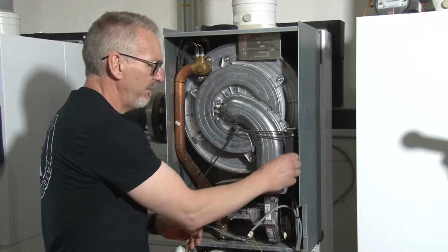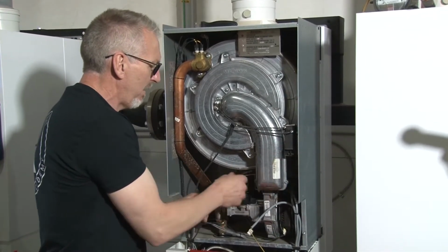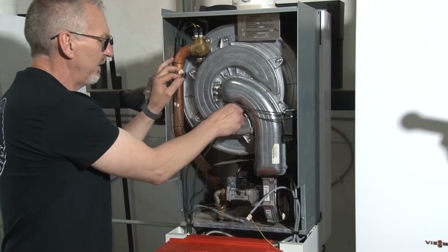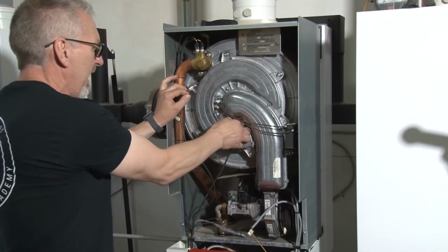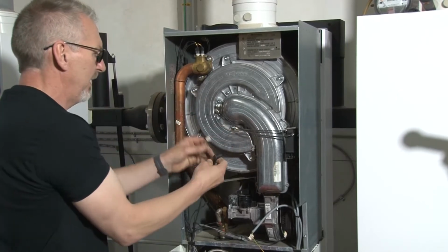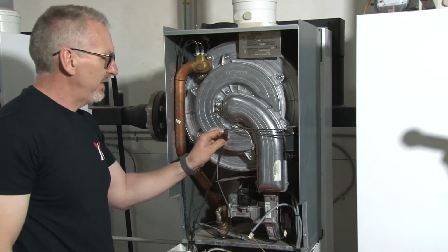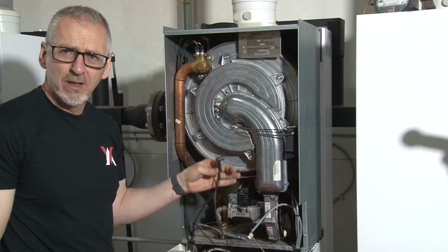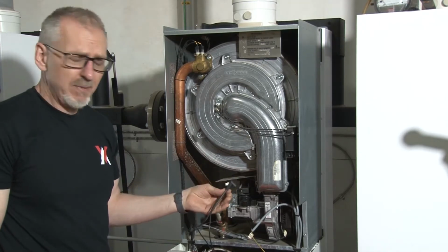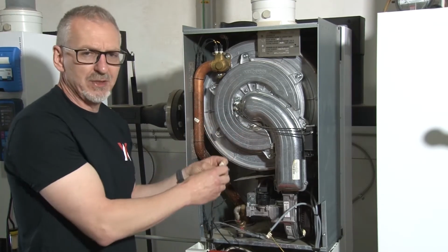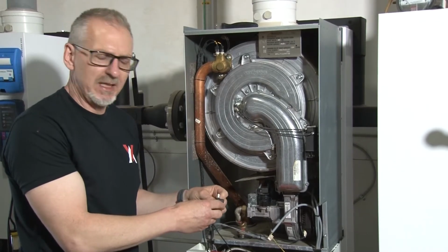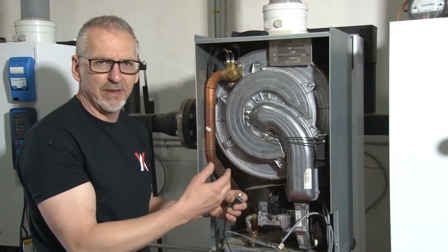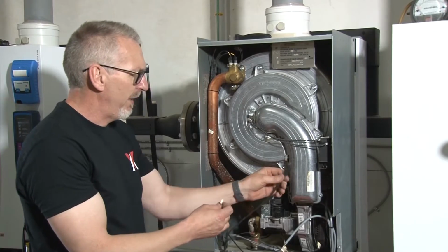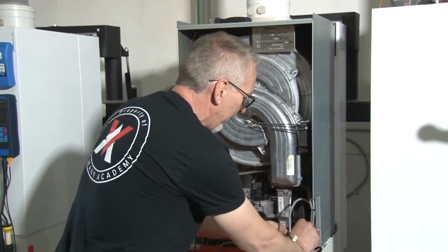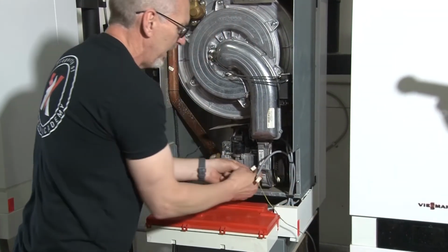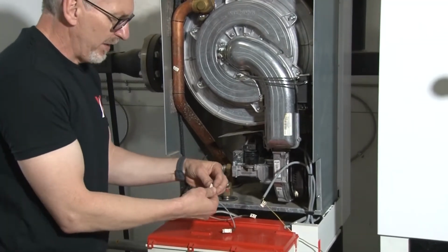We also have this plug, and that's part of the same plug. It goes in the same spot as your ionization electrode. So these two actually feed the flame signal back to your combustion controller to let the blower know we got good flame. And whichever one has the strongest flame signal is the one the blower will reference as far as flame. So it allows for more reliable light off versus just having one flame signal. We got two.